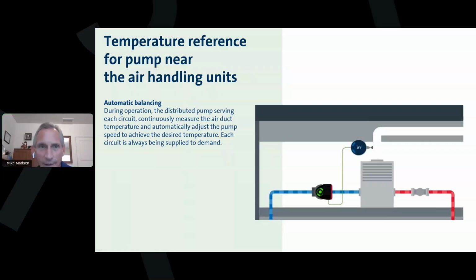Okay, heating hot water typically uses less horsepower than chill water systems. Can distributed pumping be cost effective for hot water systems too? Yes. The low-hanging fruit is the chilled water because of the delta Ts and the flows. So we're promoting it most in chilled water, but we're also doing heating water. I think our guys are from around the country, but on both of the coasts, we're seeing heat pumps being applied more and more as we push towards electrification. So distributed pumping also makes a lot of sense for heat pump applications, for both chilled water and heating water.